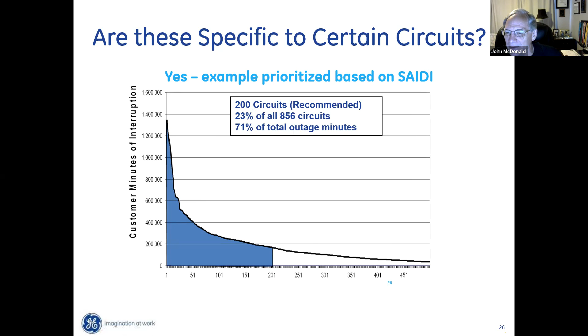That's a lot of circuits, a lot of money to automate that utility. We said, well, let's study this first. And we find that only 23% of the circuits account for 71% of the total outage minutes. That's pretty insightful. So if we automate only 23% of all the circuits, we're addressing almost three-quarters of all the outage minutes. That's a much better use of money, a much better investment by the utility.